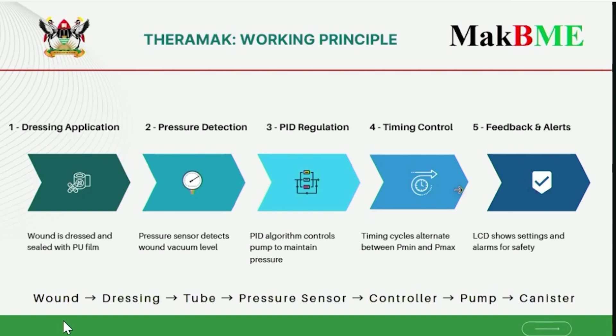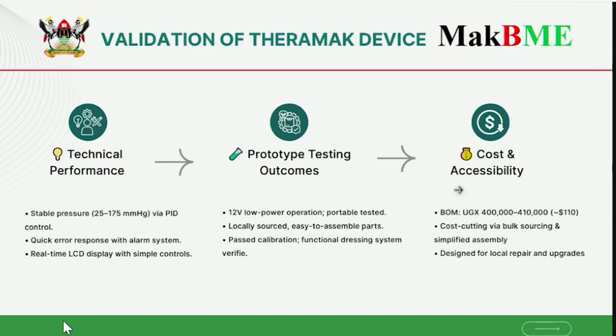Our proof of concept tests show that the device can actually provide an adjustable and stable pressure range between 25 to 175 millimeters of mercury, and its error response is quick with a fully functional alarm system. And most importantly, every part we used was locally sourced, and the bill of materials was around 410,000 Ugandan shillings. That is approximately 110 US dollars. But we know that with mass manufacturing, those costs can be further cut. So all this makes Theramak stand out from other solutions because it reduces healing time, it is affordable, it provides an adjustable pressure range, and it is locally available.